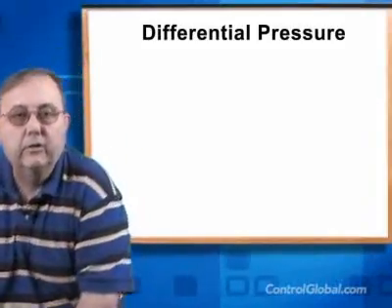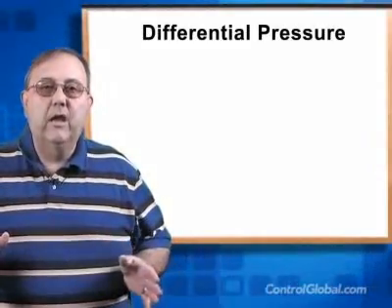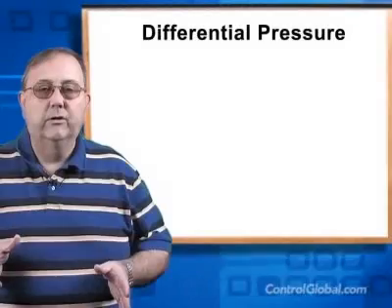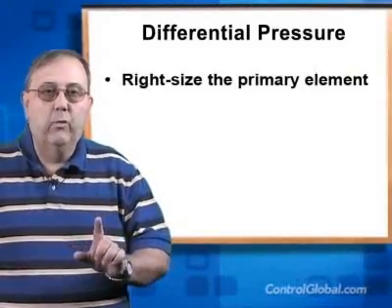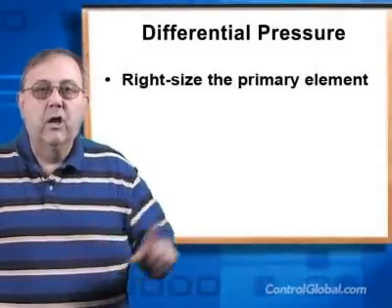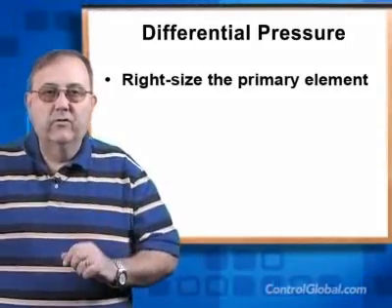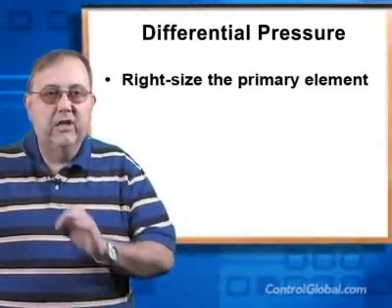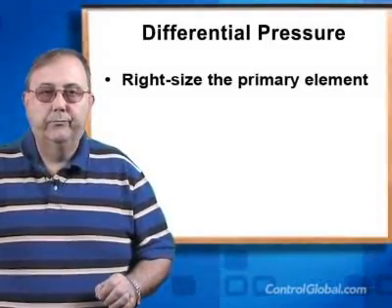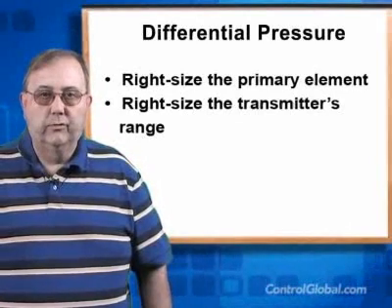Fluid characteristics play a huge role in determining the accuracy of a differential pressure flow meter installation. Be sure that the flow rate of the fluid is within the accurate flow range of the flow element. Do not oversize or undersize flow elements, even if you expect more flow in later years. And make sure that the transmitter is properly ranged, too.